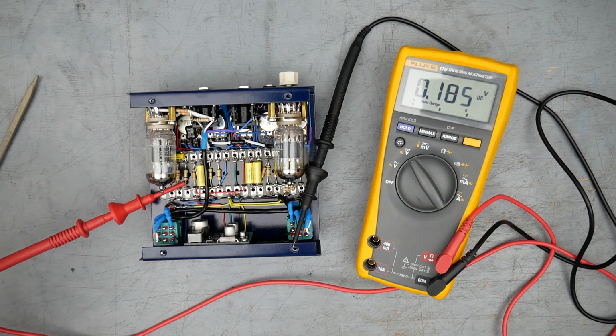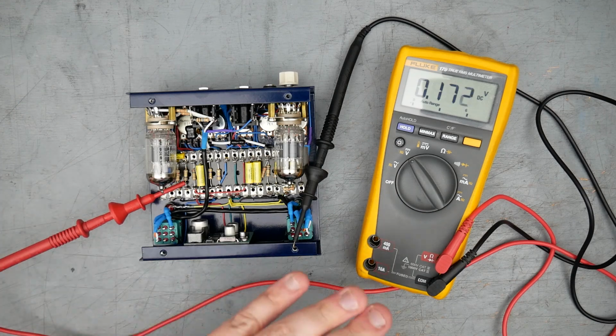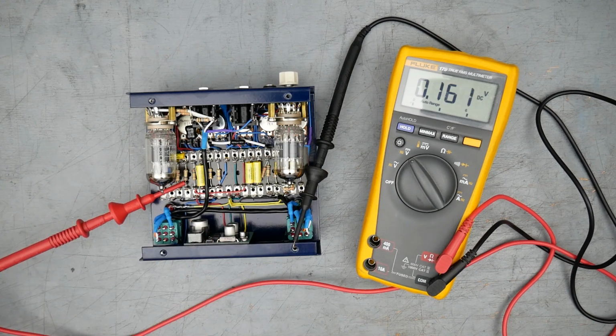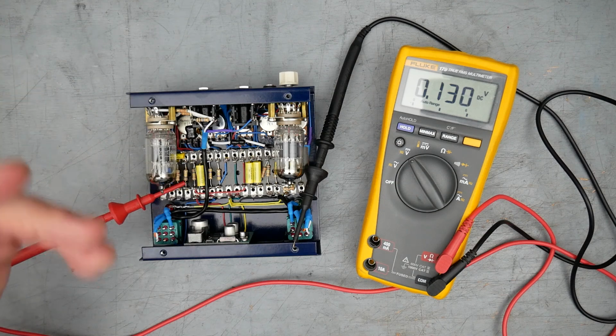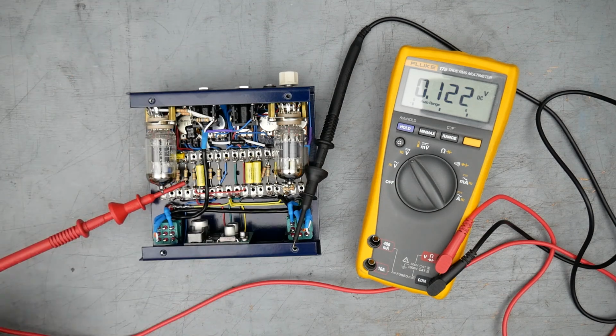We can perform a second test to figure out which one it is: let the tubes cool down completely and then provide power, which will immediately charge the circuit up to potentially even a little bit higher than 270, and then pull out the power again to see how quickly the filter cap drains.